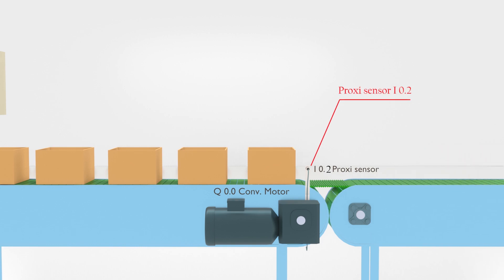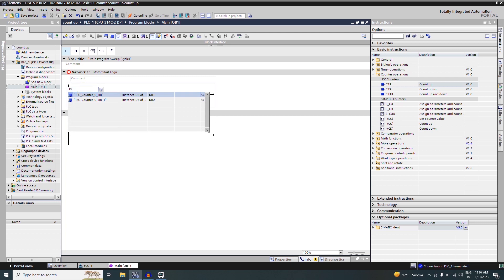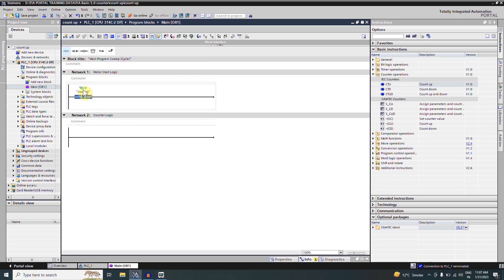Let's go to the TIA Portal software and make a ladder logic for today's problem. In network number one we want to make a logic to start the motor, so we will make a simple hold-on logic. First we will insert I0.0, which is our start push button, and next we will insert a coil and assign it Q0.0 PLC output to turn on the conveyor motor. To hold on this, we insert a branch.